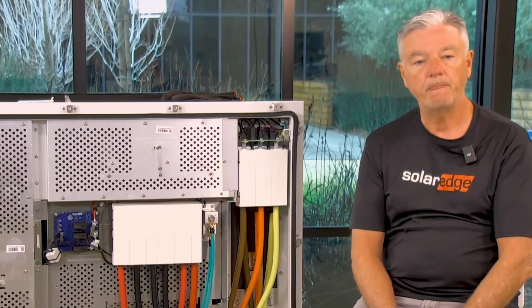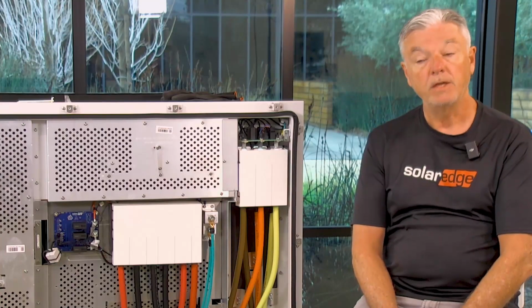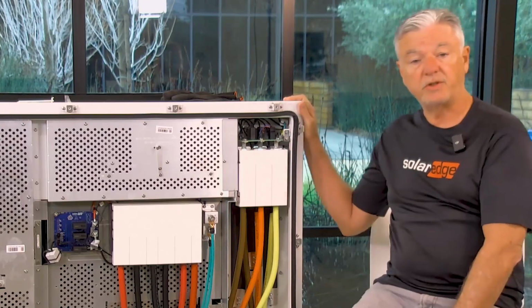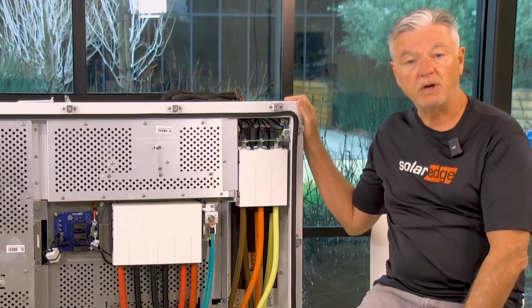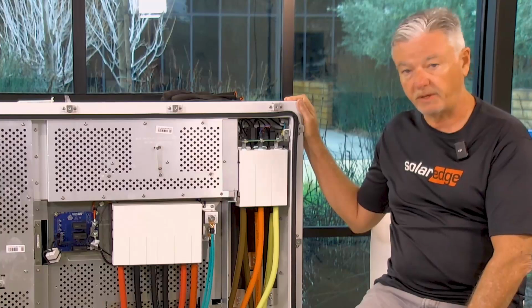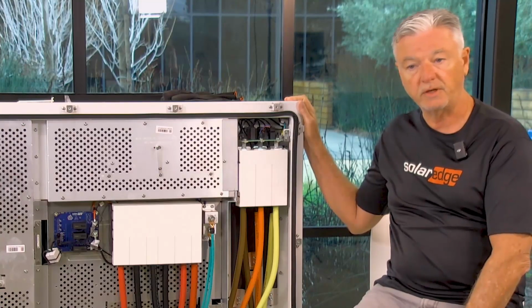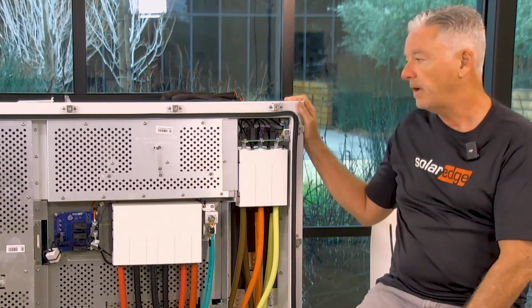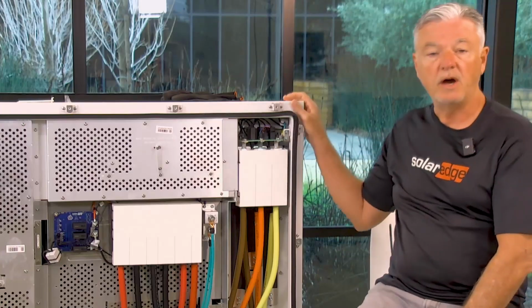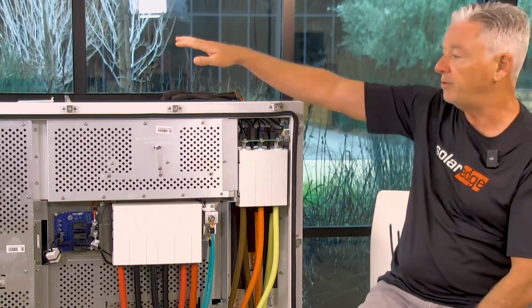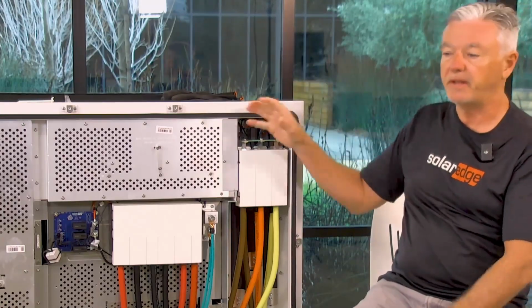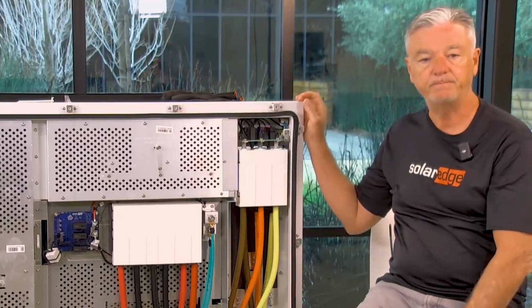Do you have any advice on mounting the inverter? Yes. So the inverter is 384 pounds. It requires some equipment to lift it, like a forklift or some kind of a lifting device. And then, of course, a rated harness or strap that you would use with the lifting eyes to lift it up and then place it onto the racking.